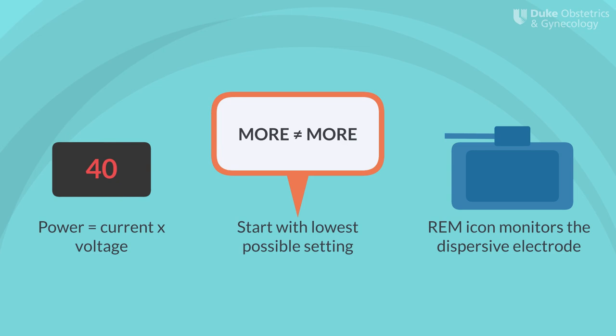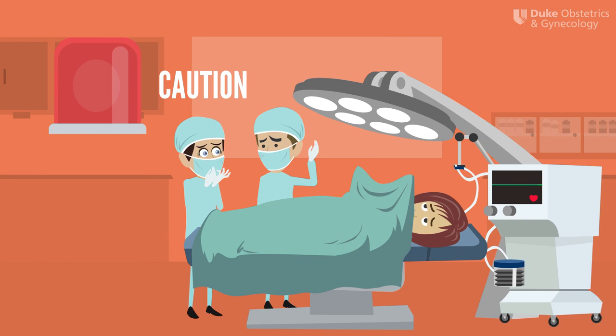The REM, or return electrode monitoring icon, monitors the dispersive electrode to ensure that it remains in contact with the patient, providing a large surface area to disperse the returning current. The icon is green when the dispersive electrode is safely in contact with the patient, and red when the electrode starts to peel off. As you've probably seen in the OR, the ESU will stop the flow of current when the pad is not appropriately in contact with the patient.